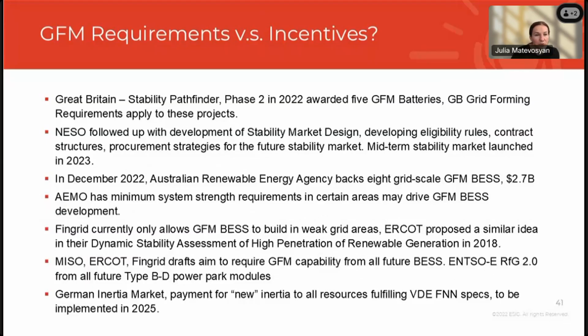Okay, so I'll switch to requirements and incentives, and then just leave some time for questions. National Grid ESO, I guess, was the first one where they ran the Stability Pathfinder. So this was a series of tenders, three, and then this phase 2 that they ran concluded in 2022, awarded 5 grid forming batteries that would provide this grid forming capability, and they need to comply with specifications for grid forming that National Grid ESO has defined.